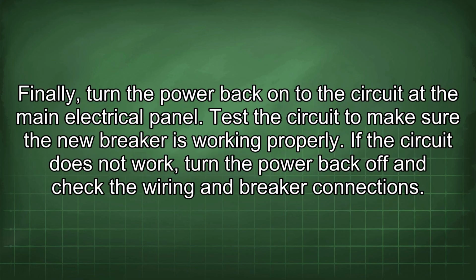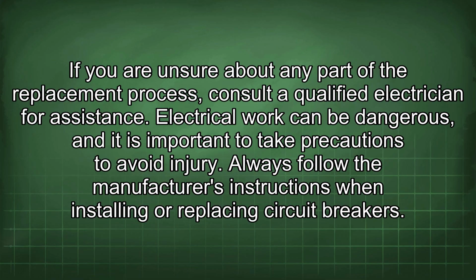Finally, turn the power back onto the circuit at the main electrical panel. Test the circuit to make sure the new breaker is working properly. If the circuit does not work, turn the power back off and check the wiring and breaker connections. If you are unsure about any part of the replacement process, consult a qualified electrician for assistance. Electrical work can be dangerous, and it is important to take precautions to avoid injury. Always follow the manufacturer's instructions when installing or replacing circuit breakers.